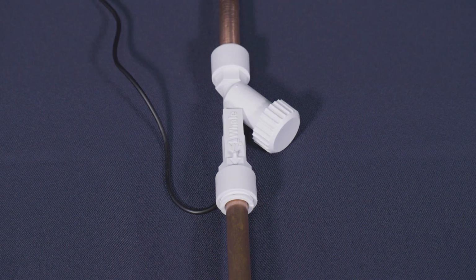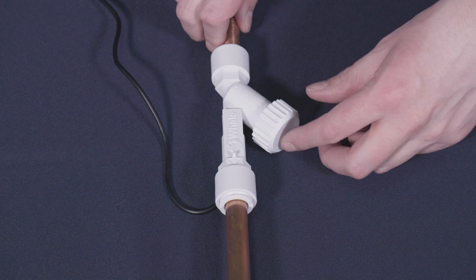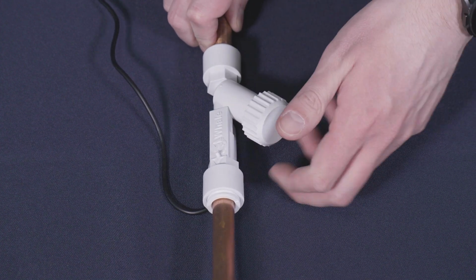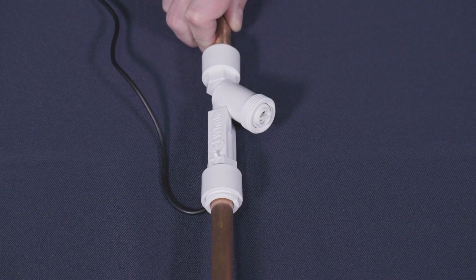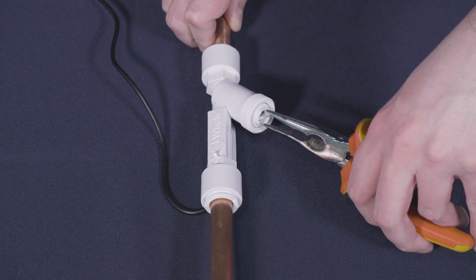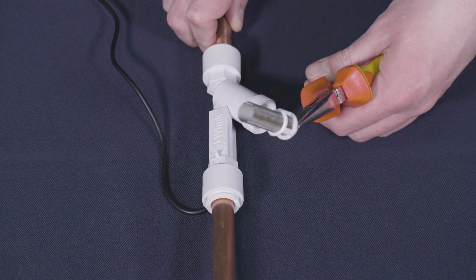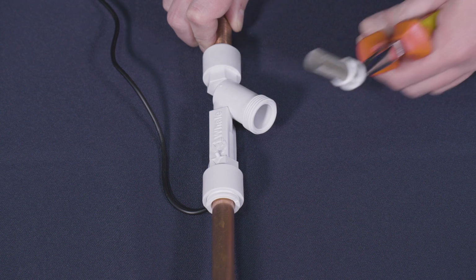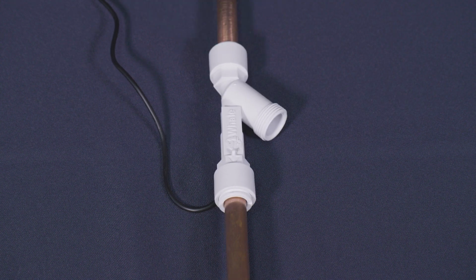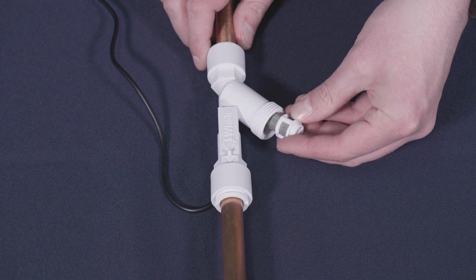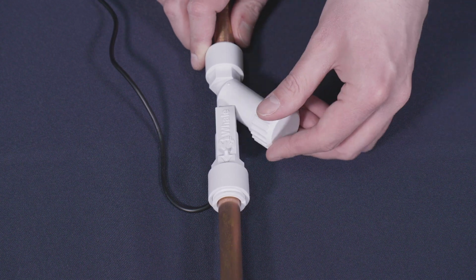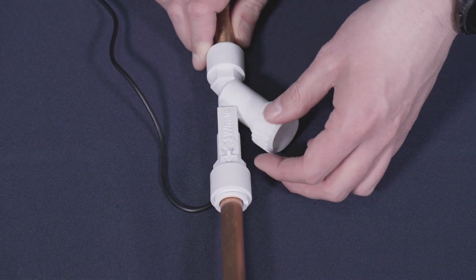To clean the switch, firstly isolate the water supply. Once this has been completed, remove the filter like so and simply clean it under running water. If the switch is still not working, then remove the switch completely and run it under the water, tapping it gently to remove any foreign objects that may have lodged in the switch. Having done this, refit and test the switch. If the switch is still not working, fit a new flow switch.